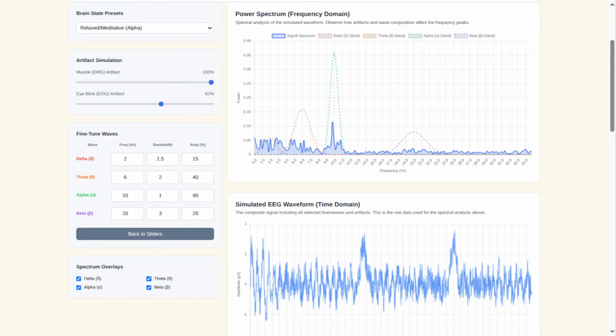Okay. So the technologist has to be constantly watching, spotting potential filter artifacts. Even the common 60 hertz notch filter for power line interference is used sparingly because it can mess with real brain activity near that frequency. It's just layer upon layer of potential issues.